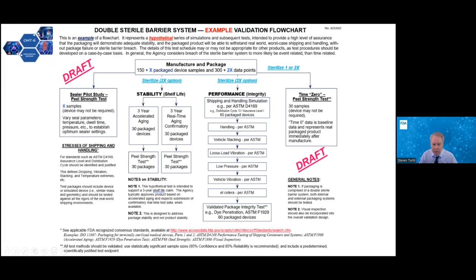And again, double asterisks there. All test methods should be validated, use statistically significant sample sizes, and we recommend 95% confidence, 95% reliability. That will give you the 30 test packages here and the 60 test packages here, and include predetermined, scientifically justified test endpoints. So these fall into two different categories for test types. That's why there's different sample sizes, 30 and 60. 60 is attribute testing, and 30 is for variable data testing.